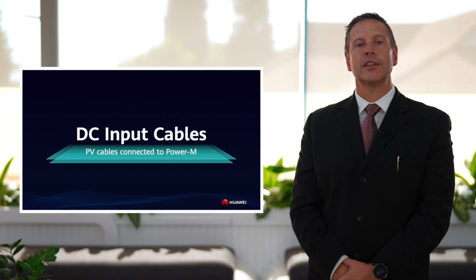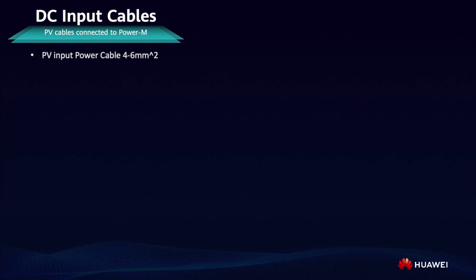Please pay attention to the positioning of the input as well as the output cables. The input and output cable headers are keyed and can therefore not be interconnected in wrong positions. DC input cables that are connected to the Power M: the PV input cable must be between 4 to 6 square millimeters. The DC input voltage is between 85 to 435 volt DC.